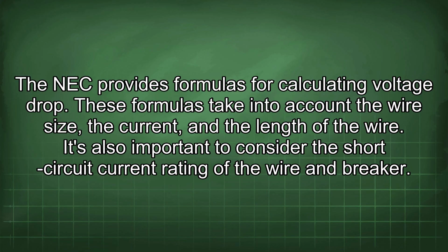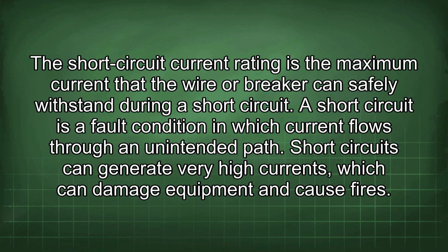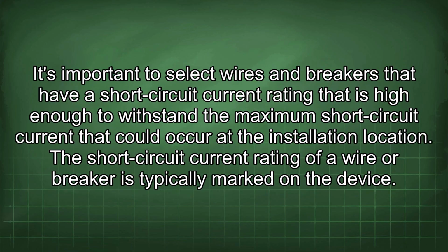It's also important to consider the short circuit current rating of the wire and breaker. The short circuit current rating is the maximum current the wire or breaker can safely withstand during a short circuit. A short circuit is a fault condition in which current flows through an unintended path. Short circuits can generate very high currents, which can damage equipment and cause fires. It's important to select wires and breakers that have a short circuit current rating that is high enough to withstand the maximum short circuit current that could occur at the installation location. The short circuit current rating of a wire or breaker is typically marked on the device.